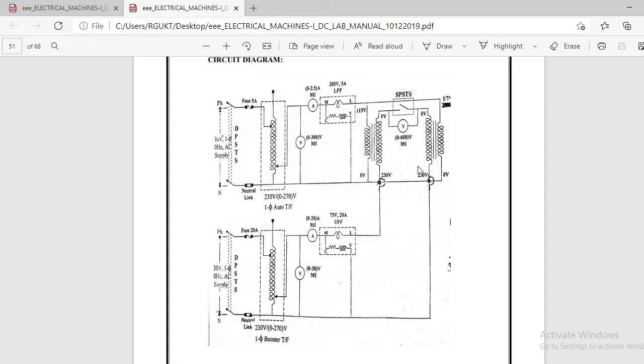The secondaries of both the transformers should be connected in series opposition. How do we check the series opposition condition? Take the 230 volt terminals and the finishing 0 volt terminals, and connect them through a switch. Across the switch we connect one voltmeter, 0 to 600 volts, MI, moving iron. When this voltmeter shows zero, the two windings are connected in series opposition. If the voltmeter indicates 100 volts, then they are in series additive, and we need to change the winding terminals.